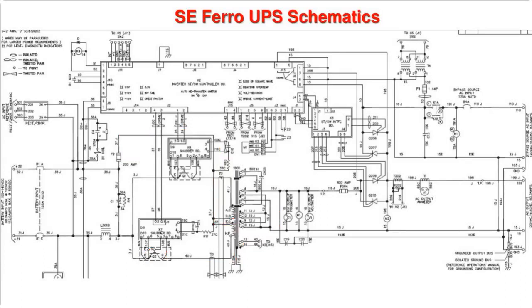Okay, so really the output of this system will be a square wave that looks like that. Sorry, not on that side, that's on that side. Okay, but then this is a ferroresonant transformer, and it has a capacitor bank in here. And what that transformer does is it regulates the output and converts it into a sine wave. So we have a square wave on the primary, but on the secondary we're going to have a nice sine wave coming out here. And we have E1, which is a frequency meter. M1, M stands for motor, so that's actually a fan. I know we probably should use F, but we use F for fuses. So an M is a motor for a fan, and then V1 is a voltmeter on the output of the inverter. Okay.